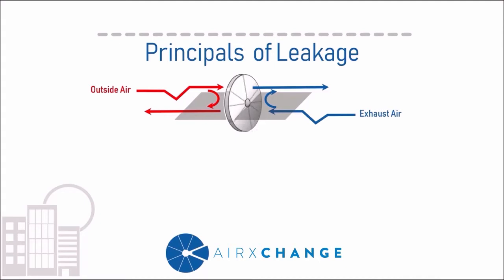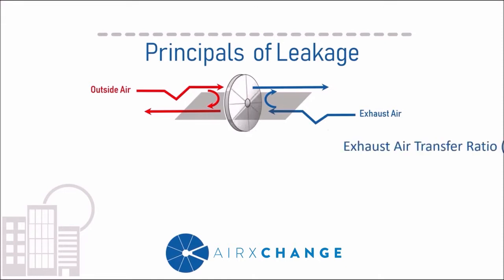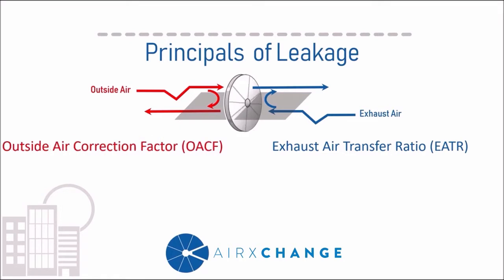It's important to keep in mind that both air streams are going to exhibit this characteristic, which is commonly referred to as leakage, cross-contamination, and a thousand other arbitrary terms. The technical term on the building side is the Exhaust Air Transfer Ratio, and on the outside air side it's the Outside Air Correction Factor. Most folks abbreviate them to EATR and OACF respectively.